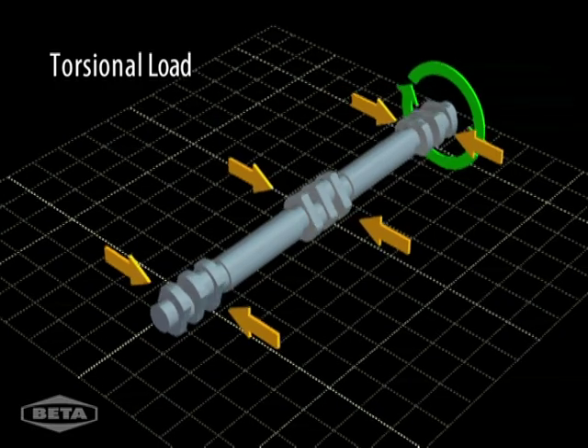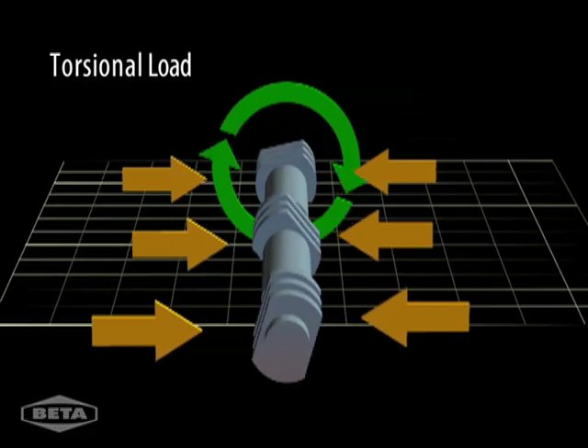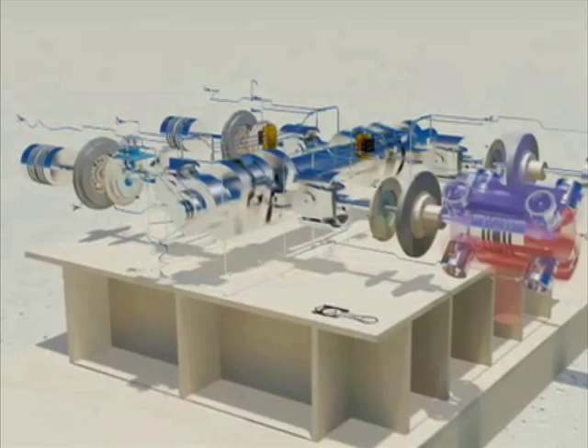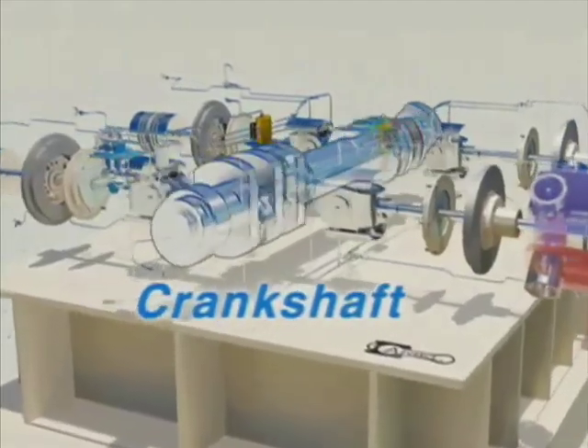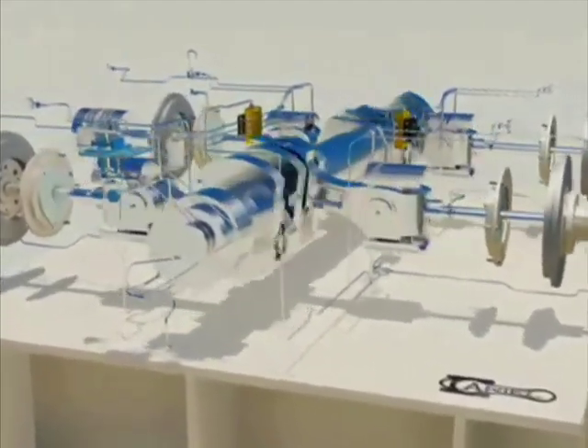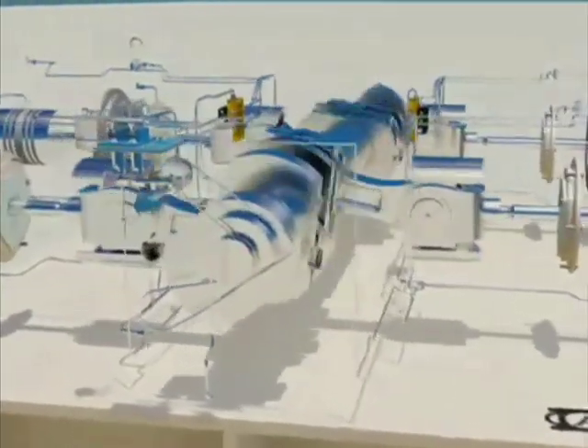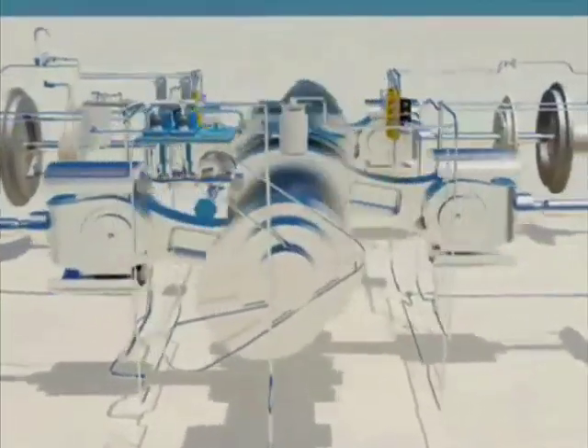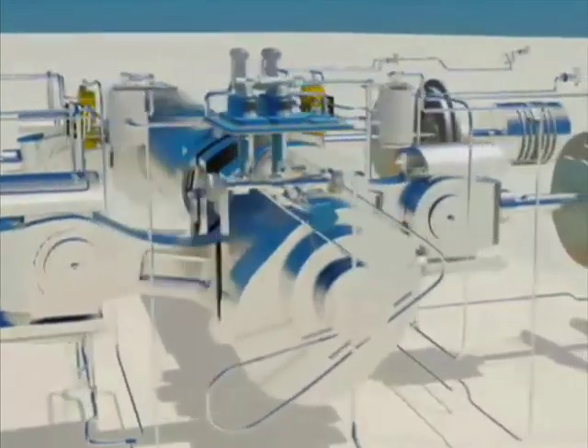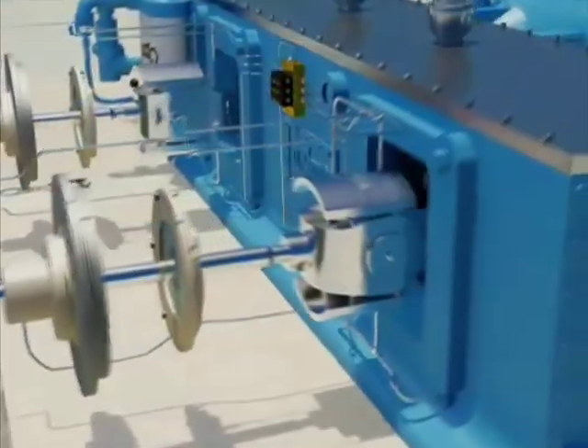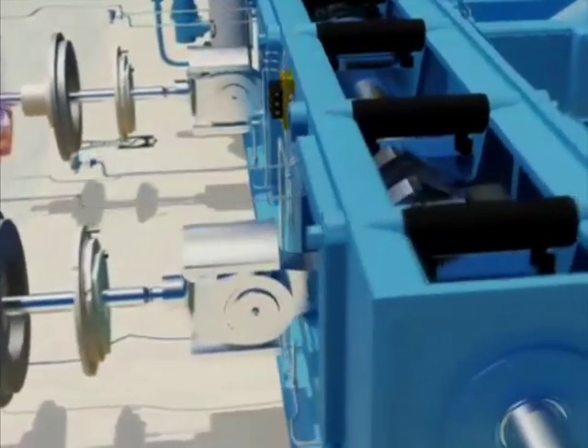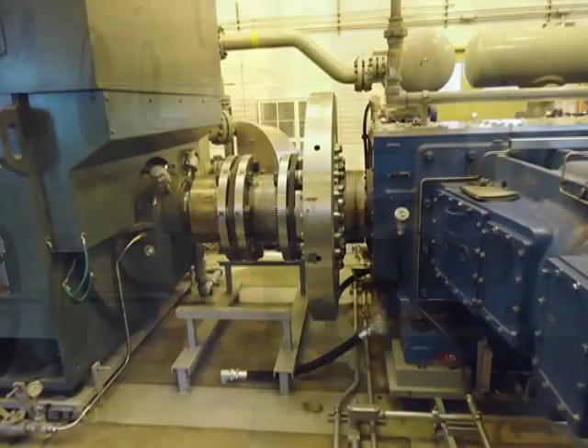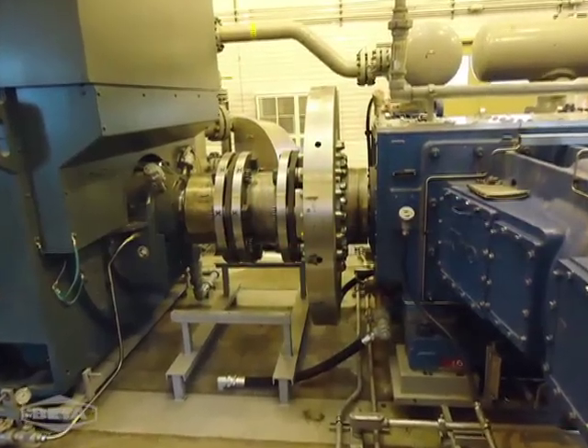In this compressor, the load from each cylinder acts on the crankshaft, resulting in a torque that can cause vibration problems. Each machine will have a unique load profile. A torsional vibration analysis considers how this combined load interacts with the crankshaft, the engine or motor, the coupling, and the resulting stress and vibration on the system.